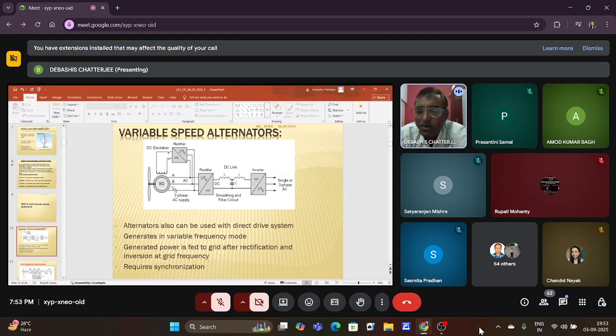This AC voltage, normally if you only connect to some heating loads, that is helpful. Otherwise, in some other loads where motors are running, this randomly variable frequency and randomly variable voltage will not be of much help. Therefore, this power is rectified to DC, and then it's filtered with some standard LC filter, T, pi, whatever the configuration. After that, this DC voltage will be inverted, that is, made AC, three phase, at the desired frequency and desired voltage level to interface with either the load or the grid. So this is the basic system, okay?